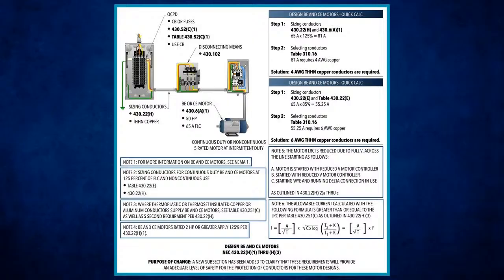So now I have established I have to use the table values. Since it's a three-phase 460 volt motor, I'm going to look at Table 430.250. I'm going to come down, pick up the 460 volt column, come down to 50 horsepower. It's going to tell you it's good for 65 amps.